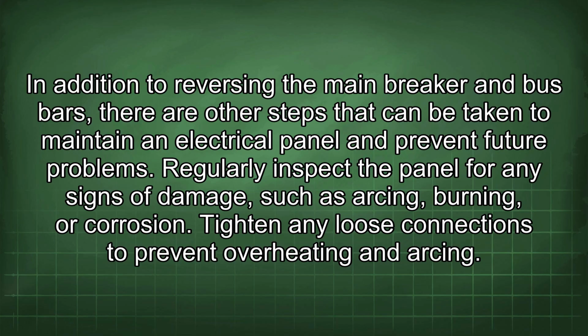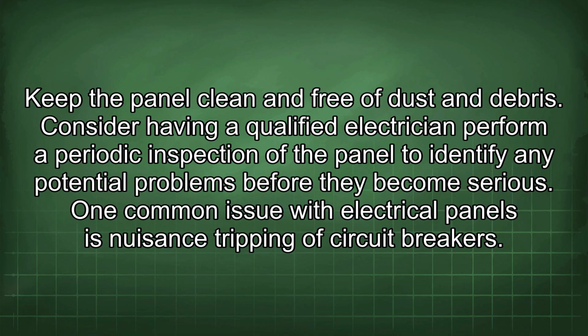In addition to reversing the main breaker and bus bars, there are other steps that can be taken to maintain an electrical panel and prevent future problems. Regularly inspect the panel for any signs of damage, such as arcing, burning, or corrosion. Tighten any loose connections to prevent overheating and arcing. Keep the panel clean and free of dust and debris.